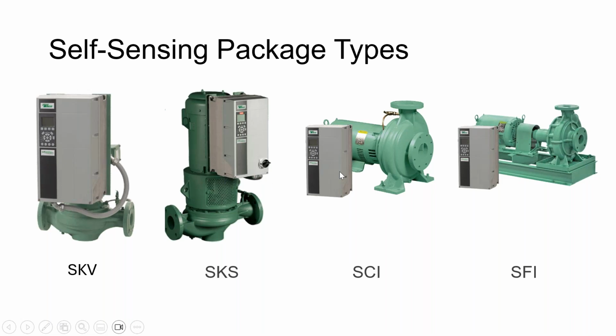So I did want to at least show you some of the other offerings that we have for the self-sensing models. So we haven't forgotten about the base mounted or the foot mounted over here. Most of them are these SKS and SKVs, excuse me. But you can order the CI, which is the foot mounted here. That's our closed coupled foot mounted one, or the FI, which is our base mounted pump. These drives do not mount directly to the pump, so they do need to be mounted remotely, but nonetheless, we do offer them for our horizontal pumps as well. I don't think we've sold them for any of the split case, but if you had a project with 300 on there, I'm sure we would do it. Quantity 300, maybe a little less than that, but nonetheless, that's probably getting a little outside the realm here.